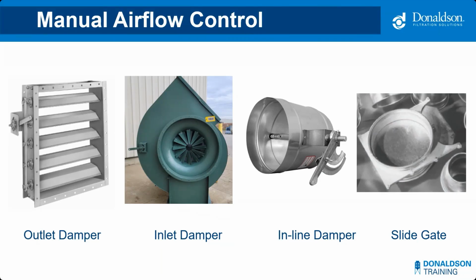For manual airflow control, the fan needs to have some type of mechanical damper or slide gate, so the operator can manually adjust the area of the duct and therefore the airflow. These dampers typically have a lever that the operator moves to open or close as needed. Building on the example from earlier, immediately following a filter changeout, the damper or gate will probably be closed to a point that maintains the proper airflow because the clean filters have a much lower static pressure. Throughout the life of the filters, the static pressure will increase and the operator will need to adjust the damper as needed to maintain that low level of airflow that keeps dust flowing through the ductwork to the collector.